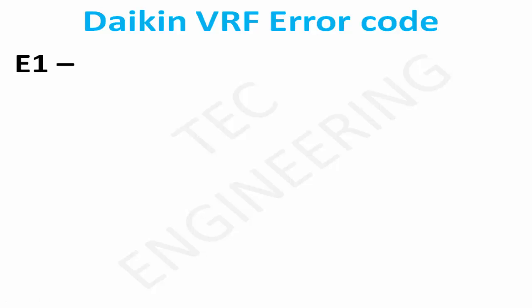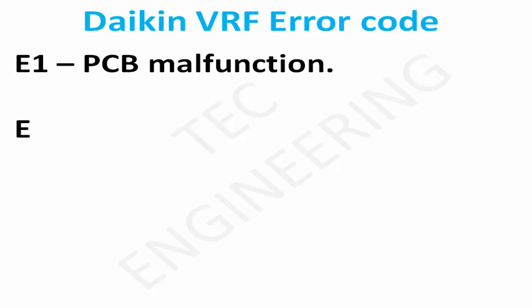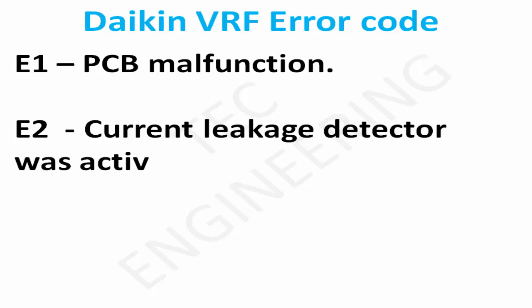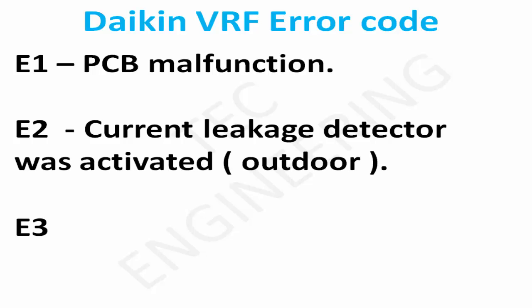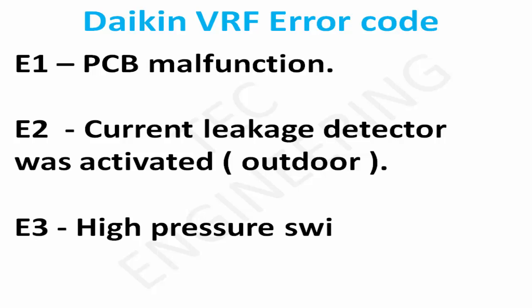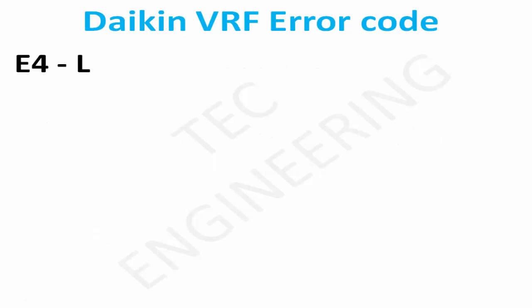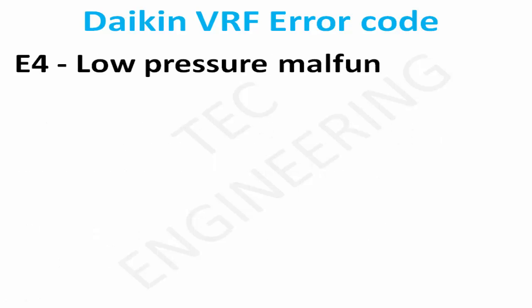E1: PCB malfunction, outdoor. E2: Current leakage detector was activated, outdoor. E3: High pressure switch was activated. E4: Low pressure malfunction, outdoor.